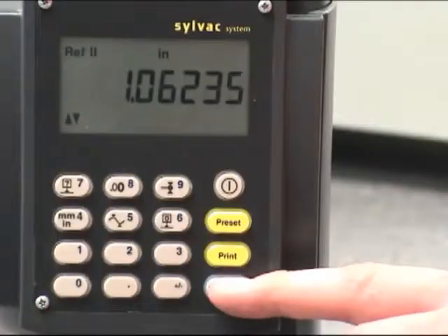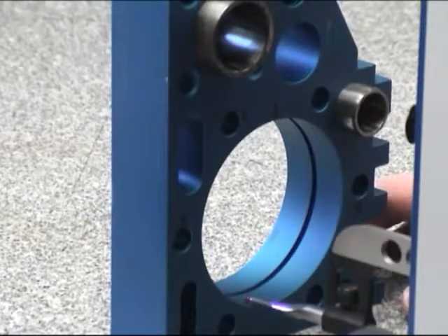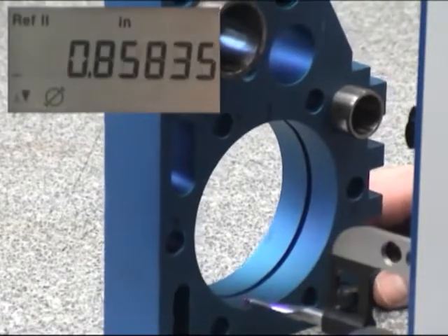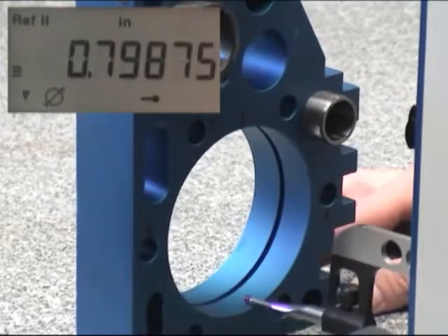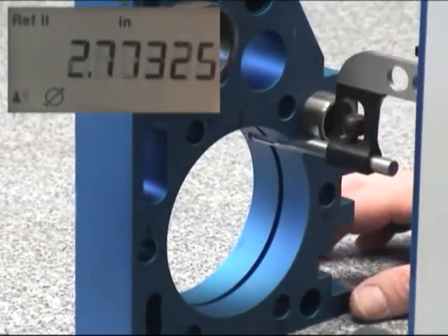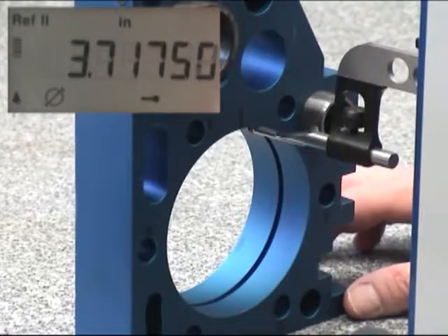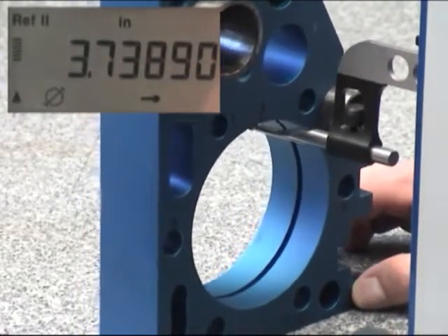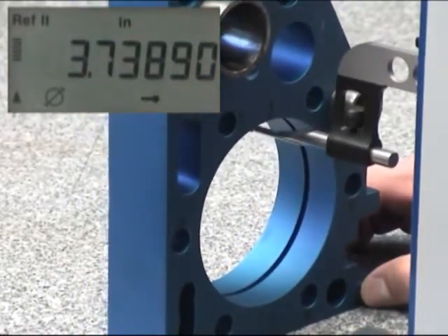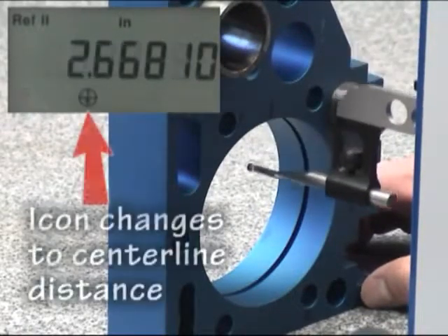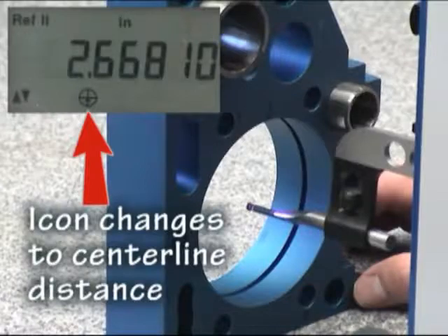Bore measuring is very simple to do on the Altea. It just requires a couple more steps. First we want to use the function button to put us in diameter mode. Now we bring the probe in near the bottom of the bore and sweep the low point. Then we simply bring the probe up, apply pressure, and sweep the high point. The diameter is locked in the display.